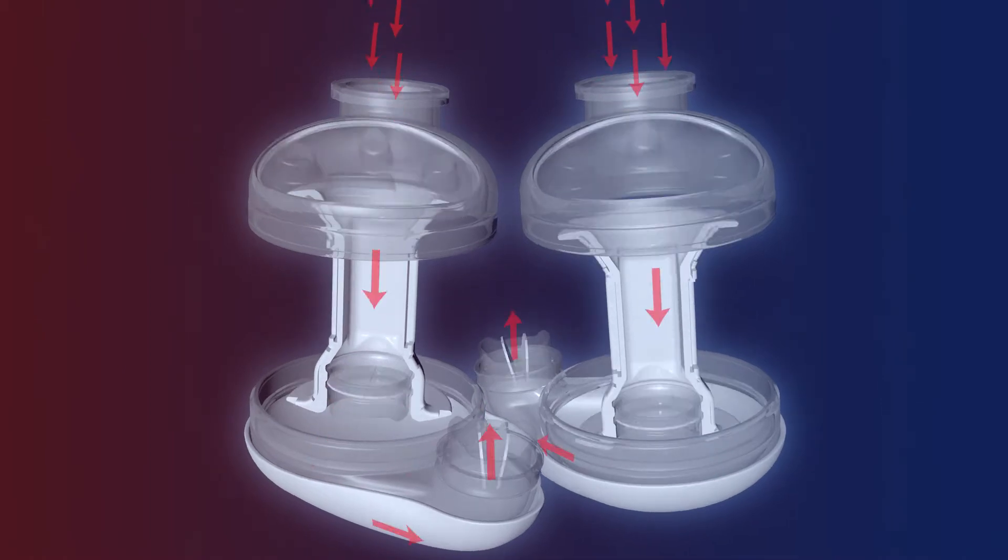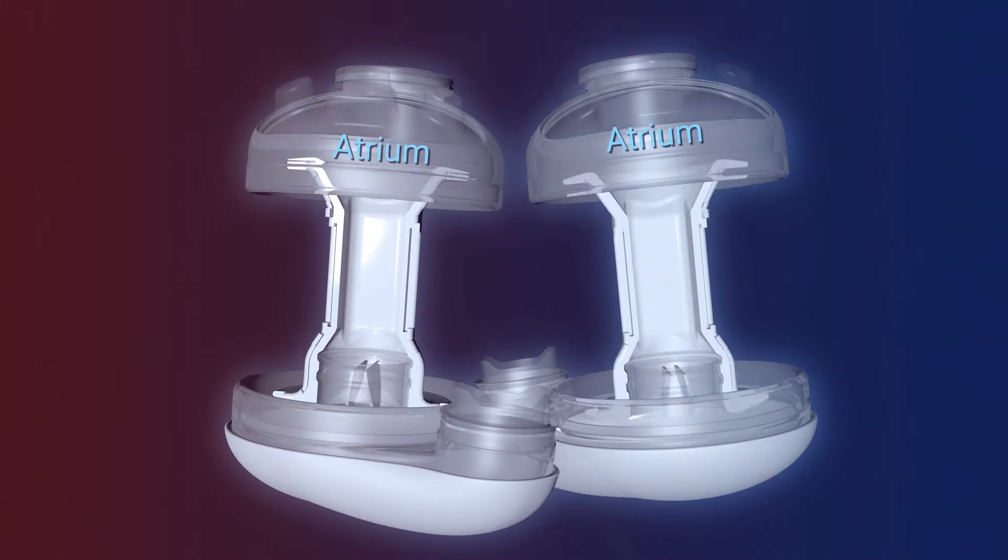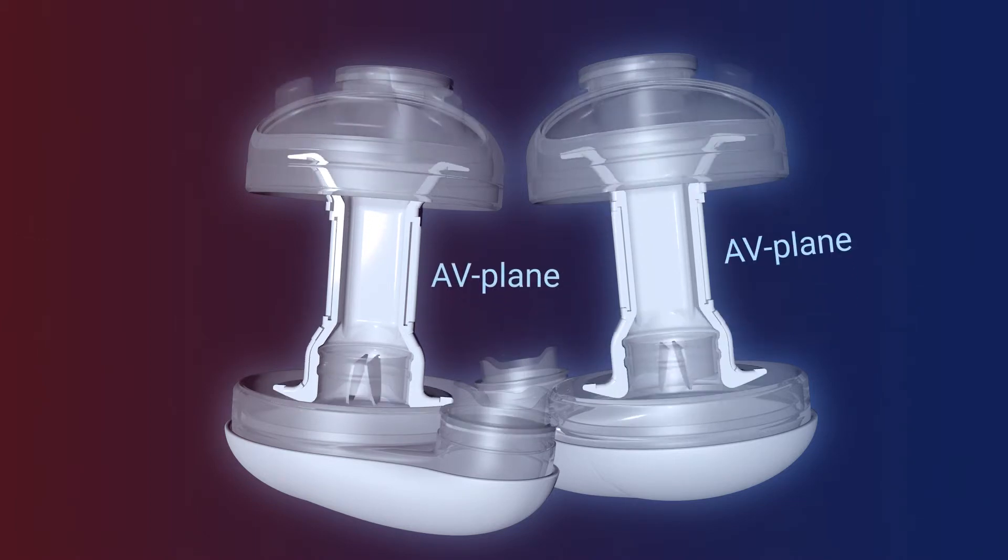As in a human heart, each pump in Real Heart TAH also consists of an atrium and a ventricle with a valve cylinder in between, equivalent to the AV plane.